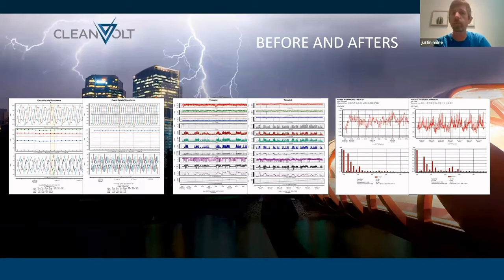If you were to call 10 power companies from coast to coast and request some power quality analysis at your facility, 6 to 8 out of those 10 power companies would show up with a Dranetz meter. And there's a reason for that. It's a fantastic meter. They do a lot of great calculations in the meter, but more importantly, the sampling rate is very fast. When you're looking for energy surges that are acting within a nanosecond of time, you have to have a very fast meter in order to be lucky enough to record these events. So 5 years ago, we invested in one of these meters.